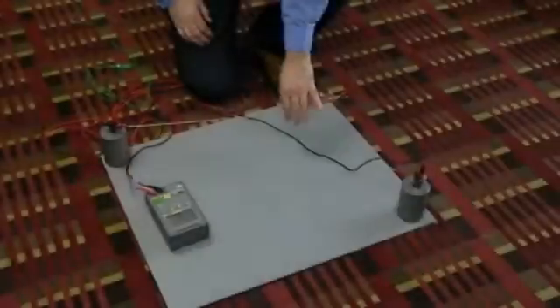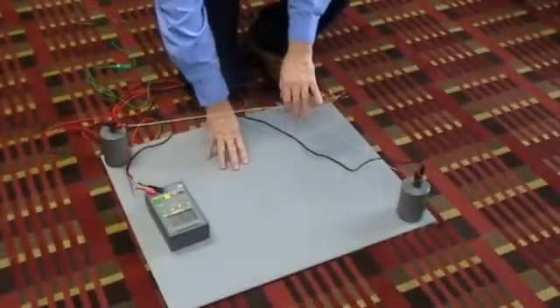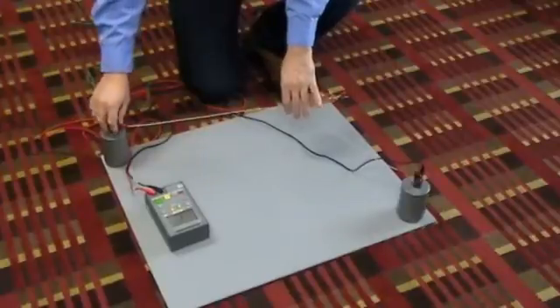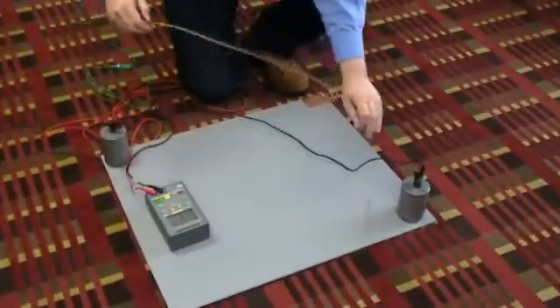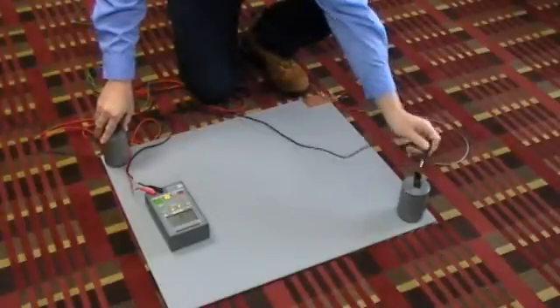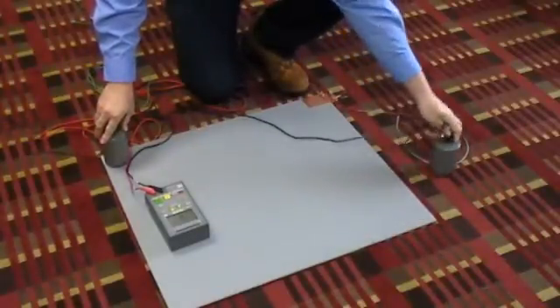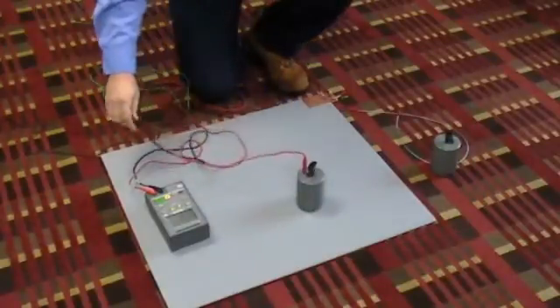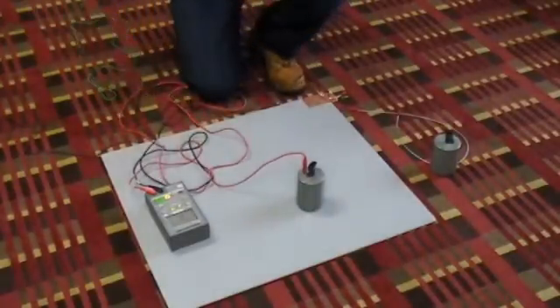The second part of this test is a ground point on the floor surface to ground. What we're going to do is remove the three-foot measuring gauge cable and unplug the negative lead to one of the five-pound weights. Place the positive lead and five-pound weight in the center of the floor.